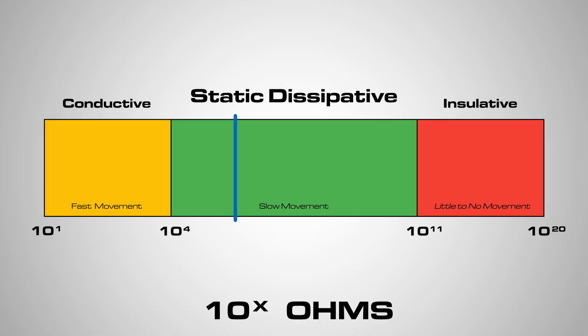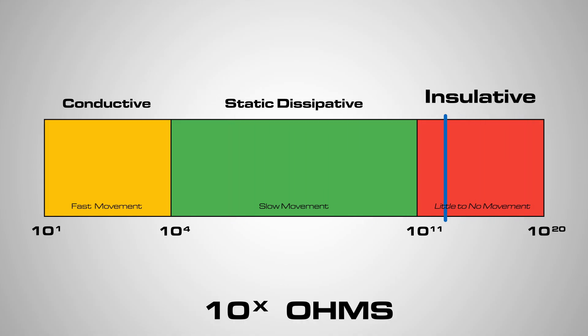Insulative materials do not allow for the movement of electrons. These are to be avoided in your ESD protected area since they do not provide a pathway for the removal of electrostatic charges. In most cases they are also sources of electrostatic charge, giving even more reasons to keep them out of your EPA. Any material measuring above 10 to the 11 ohms would be considered an insulator.